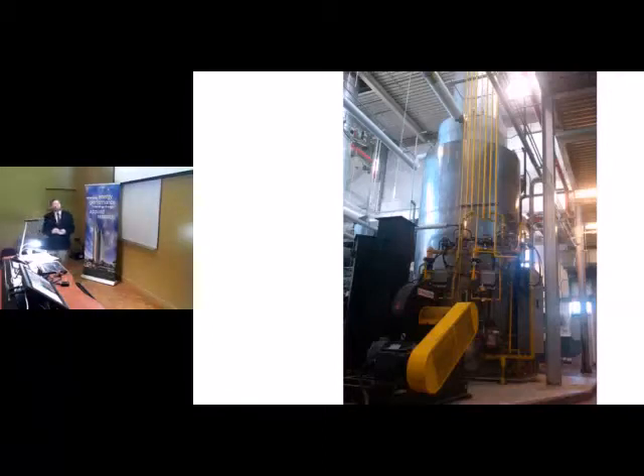What this does is it condenses the flue gas from the boilers and allows us to extract that additional energy from the flue gases. So what the net effect is for the overall power plant, we run at about 97 to 98% efficiency, where the old plant was around 65% or 60% efficient. So there's a drastic increase in the efficiency of the plant as a result of that.